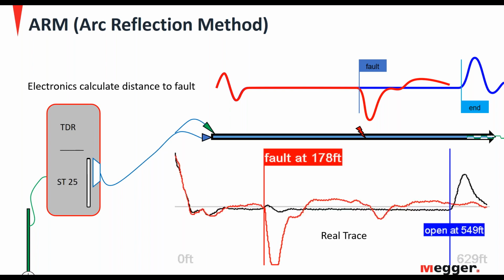And here's an example of a real one where we have an open end, again, at 549 feet, and we can see the fault at 178 feet.